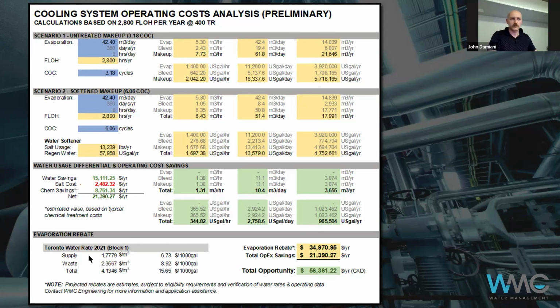Compared to Guelph or Kitchener, where you have much higher hardness coming in, anywhere with a little bit higher heat or more nucleation points for precipitate or scale formation, you could scale up probes more frequently. You need to operate the system so you don't have scaling tendencies - get your saturation index correct so you're not forming scale anywhere, and then your probes won't have problems.